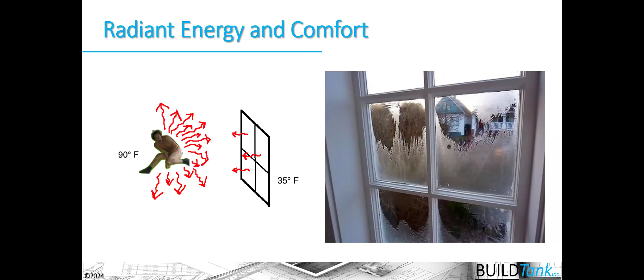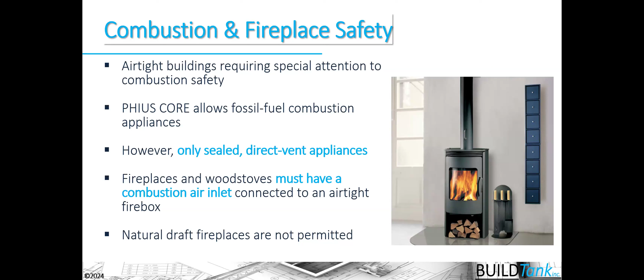It doesn't disallow the use of atmospherically vented or wood burning fireplaces, but it does say that if you're going to use a wood fireplace and still maintain a rock solid, airtight building thermal envelope, you need sealed combustion fireplaces. The doors need to be airtight and sealed, and combustion air needs to be brought directly from the outside to the firebox to maintain the flame and draft the byproducts of combustion out of the house without interacting with the indoor air. So you get the benefit of the heat from the fireplace, without indoor air being used as combustion air and drafted out of the house.